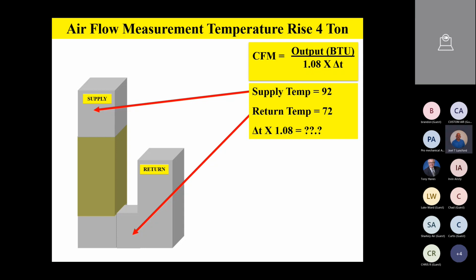So take 20 times 1.08, and that's going to give us some number. Go ahead and do that on your calculator: 92 minus 72, which should be 20, times 1.08. That gives us the next portion of the formula, which should be 21.6. I then take the output, 41,221, and I divide it by 21.6 to complete that formula.